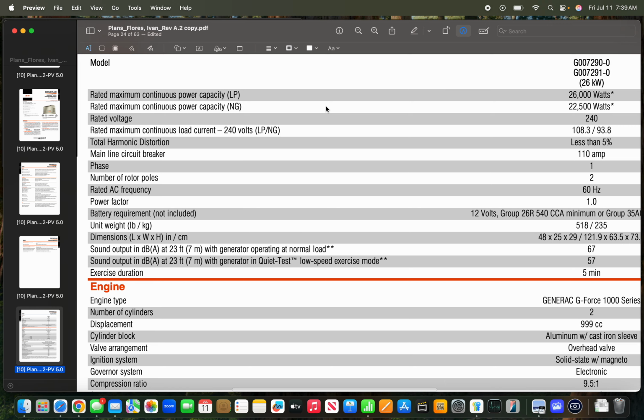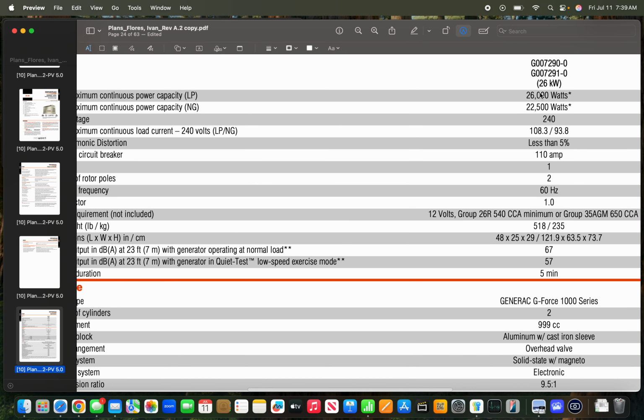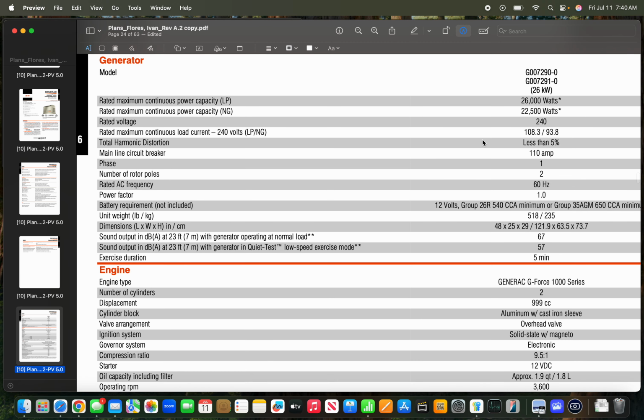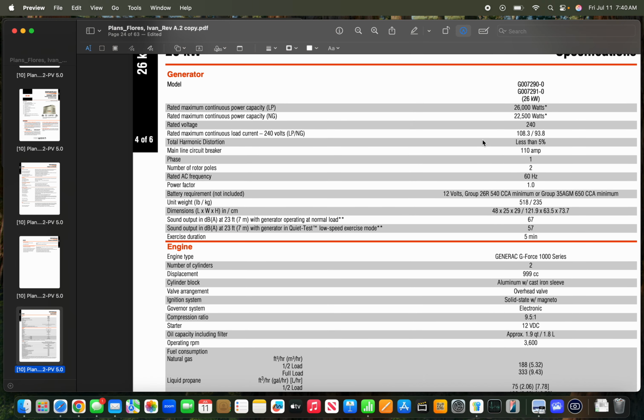It's important to note that power variances change. Natural gas drops the power rating, so they're going to use liquid propane, getting close to the maximum power output of 26,000 watts, or 26 kilowatts. If they were using natural gas, which this site isn't, it would drop off about 10% or so of the power. Not something to worry about here, but just keep that in mind.